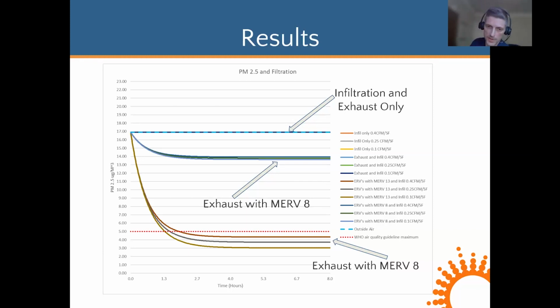And if we don't have control over the inside, if we're not filtering it, even a little bit of filtration is going to give us a little bit of a break from the negative health effects. It's also important to remember that PM 2.5 we just used as a proxy for particulate matter in general. There are a lot of other pollutants in the air that end up indoors. So these two graphs show us the importance of controlling the outside air, tempering it, delivering it to where we need it at a lower rate, and adding filtration.